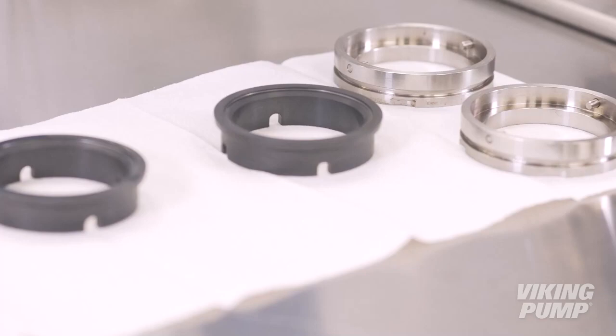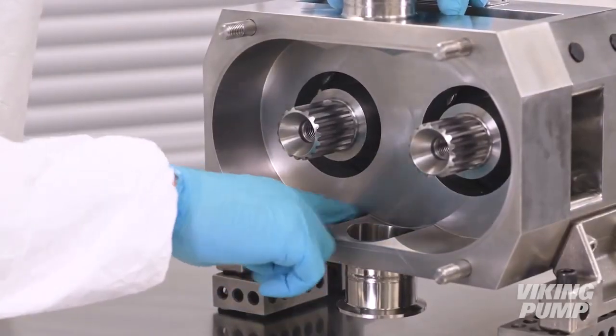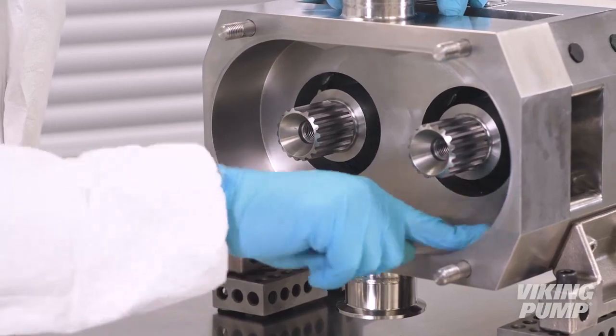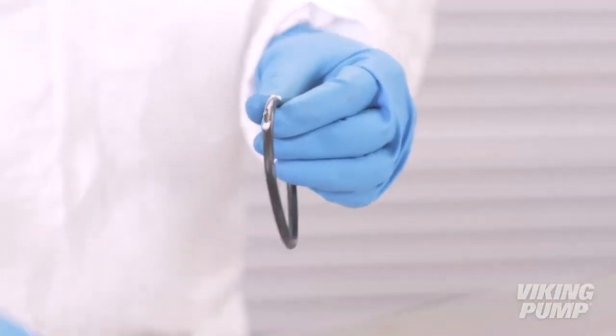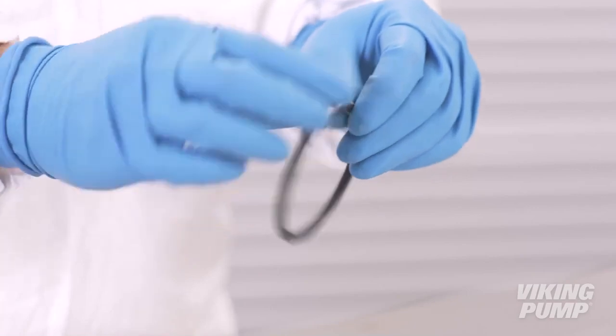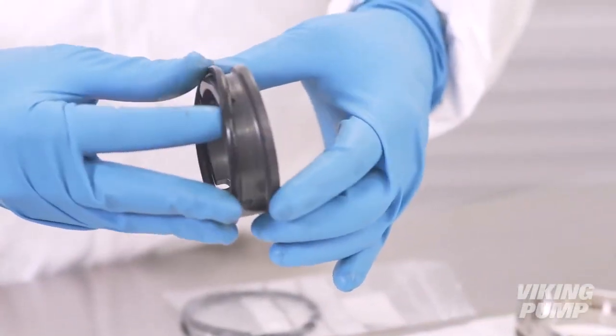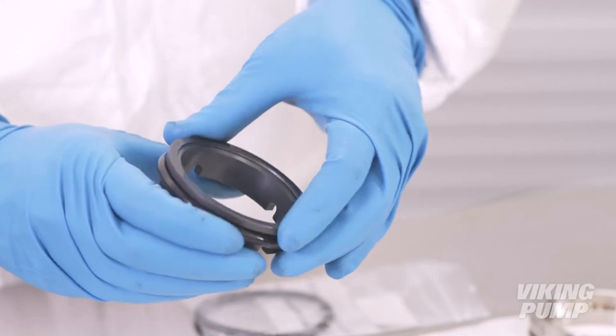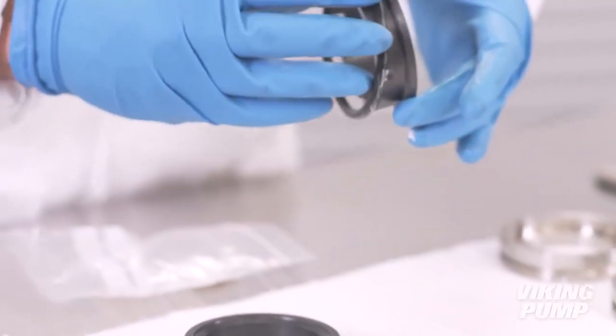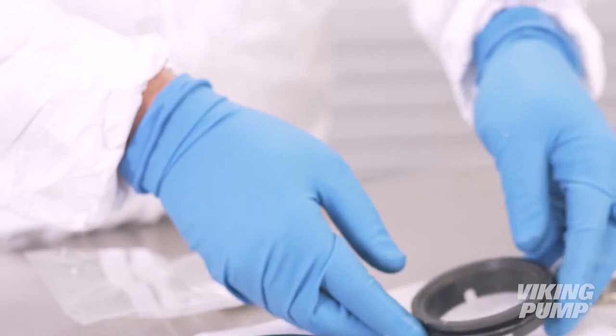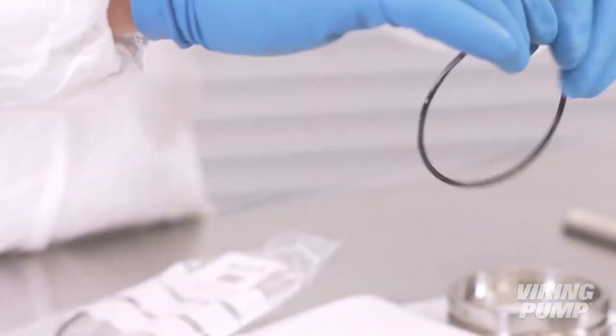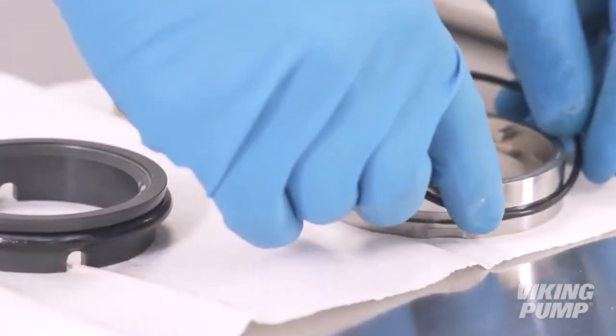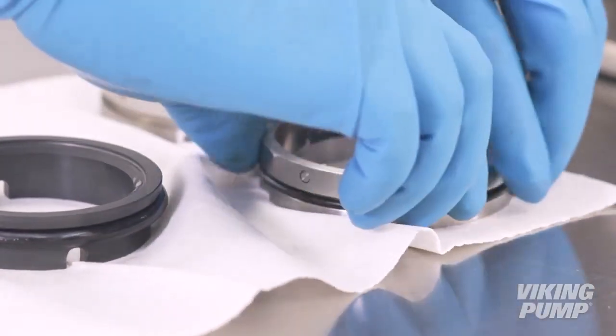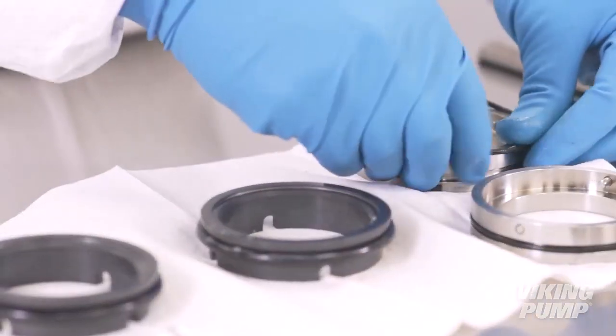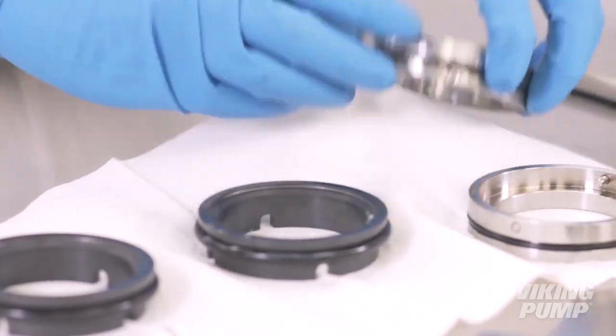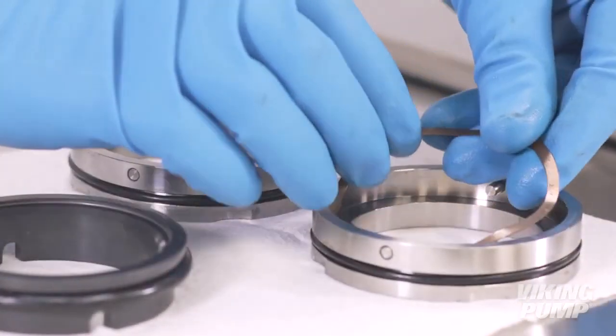Install new stationary seal assemblies. Start by inspecting the rotor case bore to make sure it is clean and free from debris and damage. Lubricate and install the seal face O-rings. Lubricate and install the seal housing O-rings. Install the wave springs.